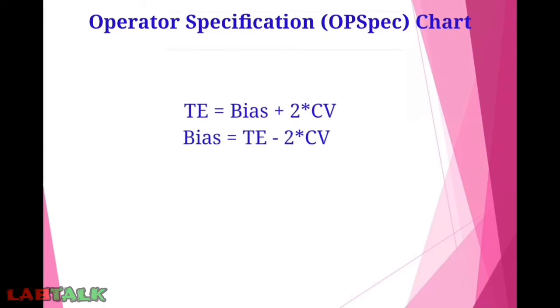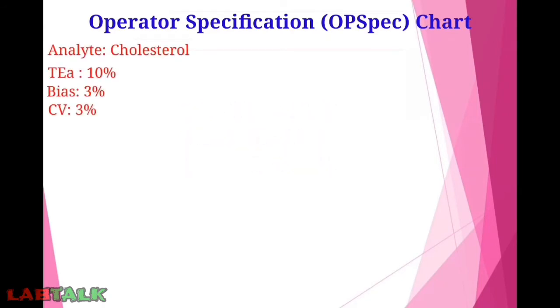Before plotting, we need some formulas. First: total allowable error = bias + 2 × CV%. Rearranging, bias = total allowable error − 2 × CV%. And CV% = (total allowable error − bias) / 2. These three formulas will be used in plotting the operator specification chart.